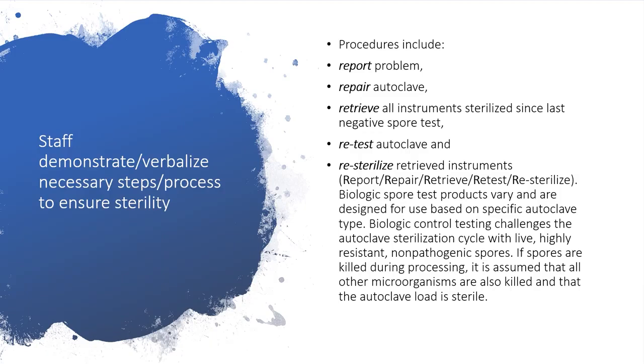The 5 R's are identified here. Report a problem. Repair the unit by either sending it out, having a technician come to the facility, or replacing the unit. Retrieve. Identify the date of the last negative spore testing. Remove those instruments sterilized in the faulty unit and pull out of stock.